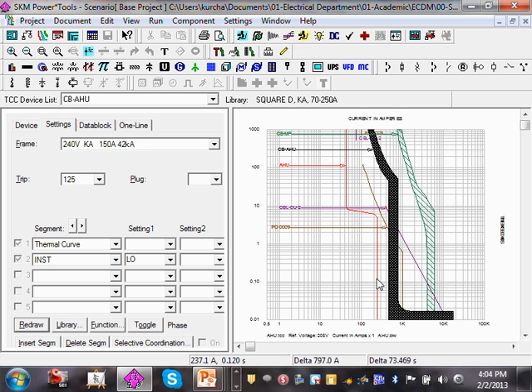Just a side note, when Xcel and all the utilities size a transmission distribution system, the major decisive factor in the size of the conductor is not the load, because at 69,000 volts the amps are not an issue. The decisive factor is voltage drop because of the distances. That's an issue, right? Voltage drop and the short circuit issue. So it starts with voltage drop, short circuit, and then the full load. That's for the high voltage.